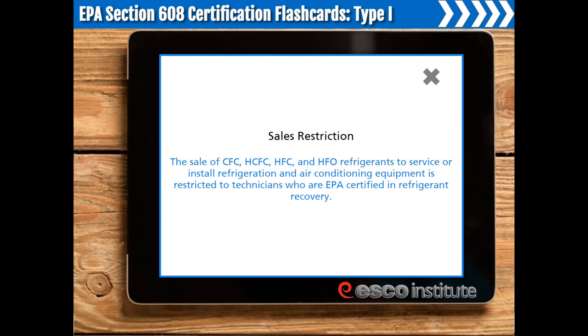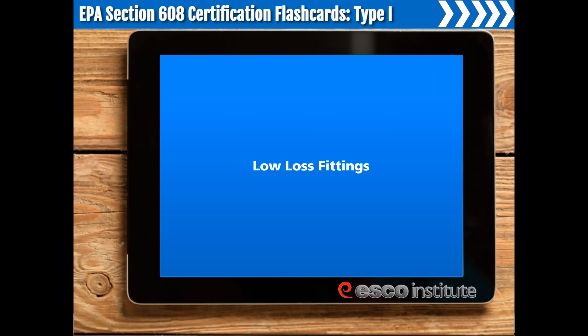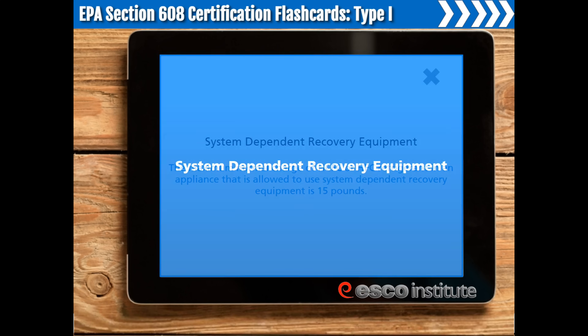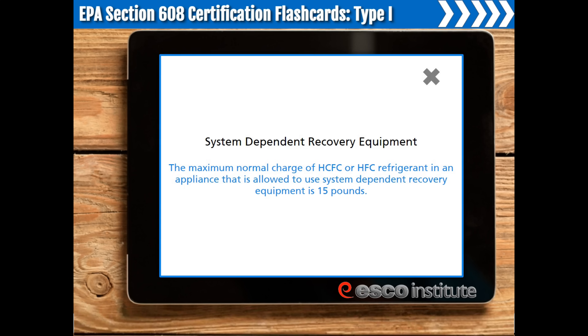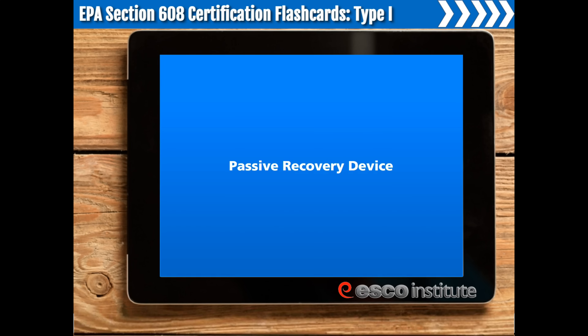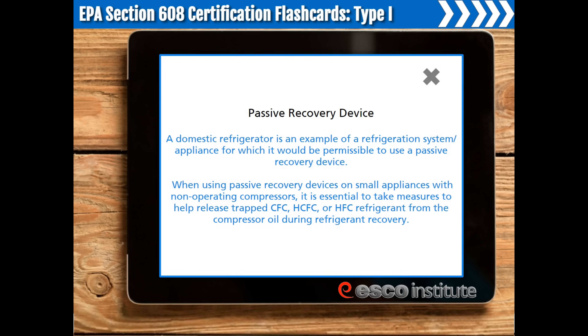Sales restriction. The sale of CFC, HCFC, HFC, and HFO refrigerants to service or install refrigeration and air conditioning equipment is restricted to technicians who are EPA-certified in refrigerant recovery. Low-loss fittings. Recovery devices used to recover CFC, HCFCs, and HFCs should contain low-loss fittings that can be either manually or automatically closed when disconnected to prevent loss of refrigerant from hoses. System-dependent recovery equipment. The maximum normal charge of HCFC or HFC refrigerant in an appliance allowed to use system-dependent recovery equipment is 15 pounds. Passive recovery device. A domestic refrigerator is an example of a refrigeration appliance for which it would be permissible to use a passive recovery device.